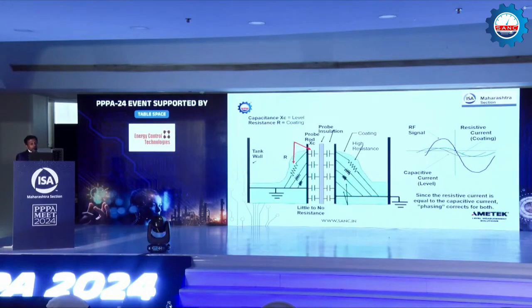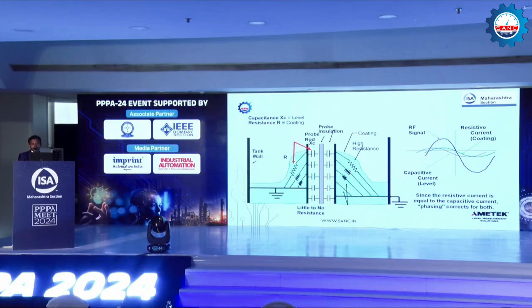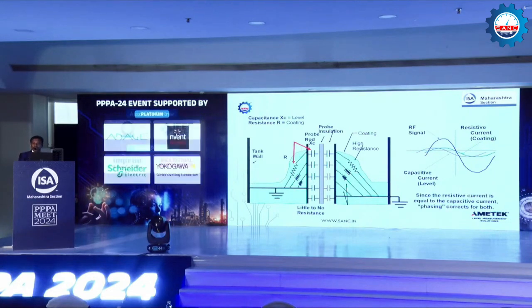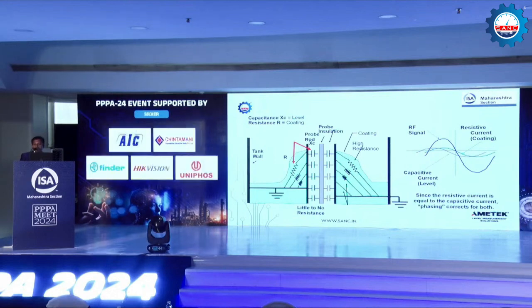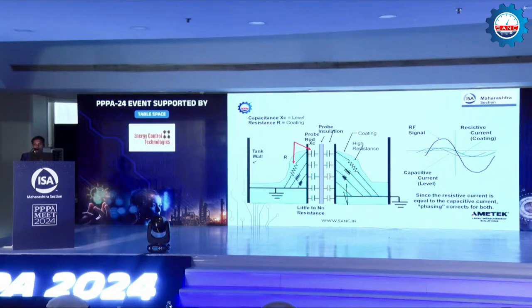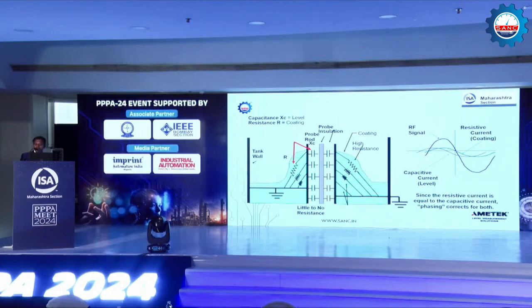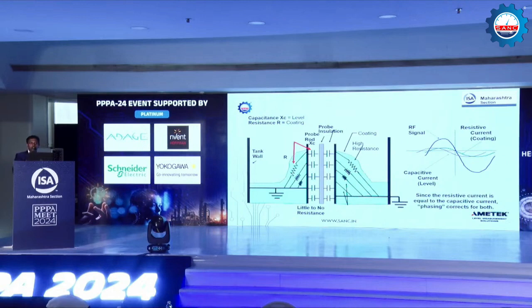In a level transmitter, as this picture shows, when you analyze the signal, we get three signals. One is the RF signal. The RF signal is nothing but a radio frequency wave, which we generate through our electronics to measure the capacitance. That is why we call it the RF, radio frequency signal. Apart from that, because of this coat shield probe technology, we get two more signals: a resistive current and a capacitive current. When you analyze them, these two are opposite in phase. So with a filter, we can eliminate them because we are identifying which is resistive current and which is capacitive. We can analyze only the RF signal, and with this RF signal the actual level is measured. This is how the coating error is eliminated in level transmitters.